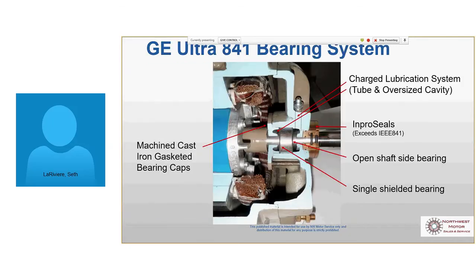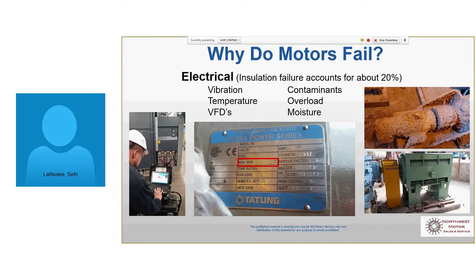So aside from the mechanical, which is like 80% of the failures, electrical is the other 20%. There's a bunch of different components that can make a motor fail due to what we call electrical. Now, I'll call thermal issues electrical, although you could call that mechanical too. You can imagine there's a motor underneath that, and there's a brake here, and a coupling guard, and a gearbox, all covered in pulp stock, which makes wonderful papier-mâché and completely seals that motor in its own little cocoon. And you can imagine how hot that gets, and it cannot dissipate heat.